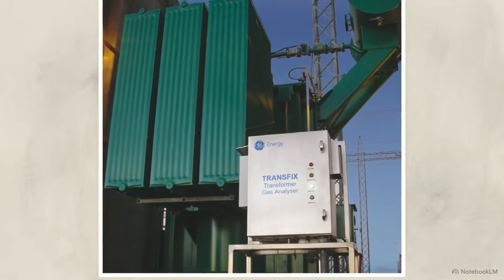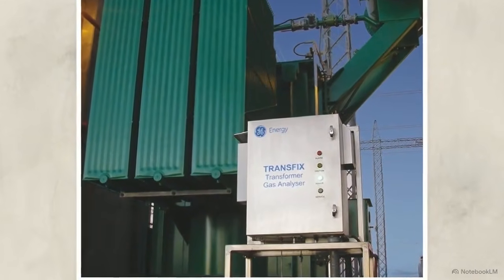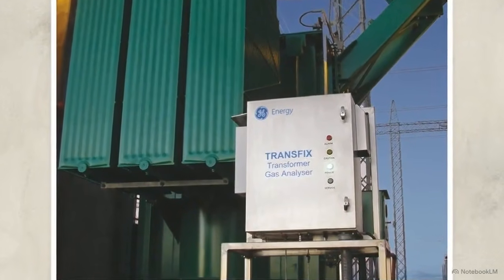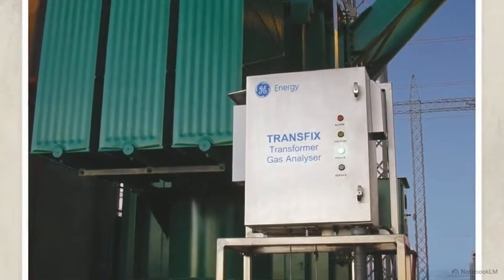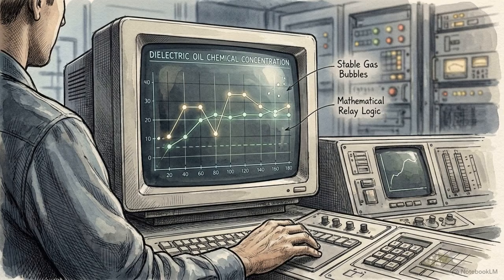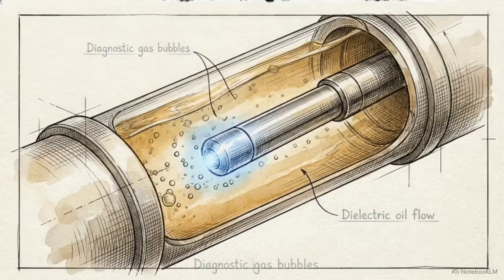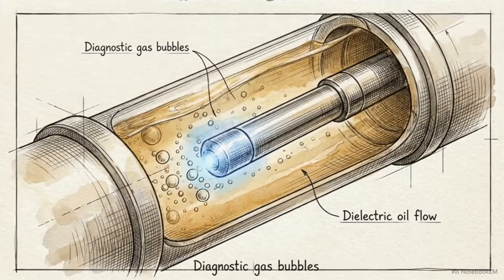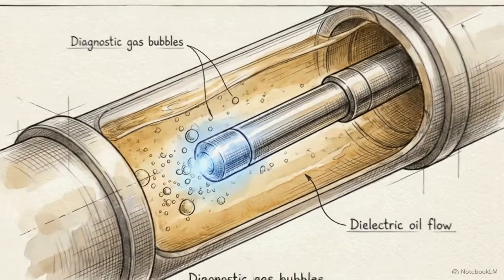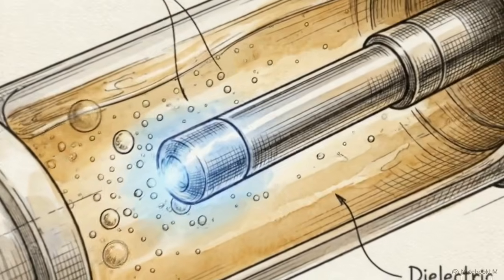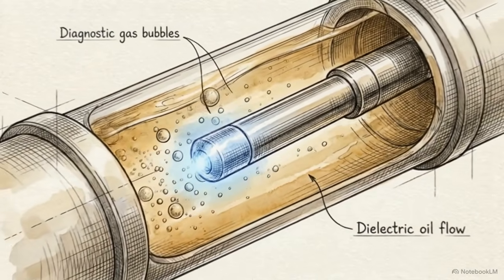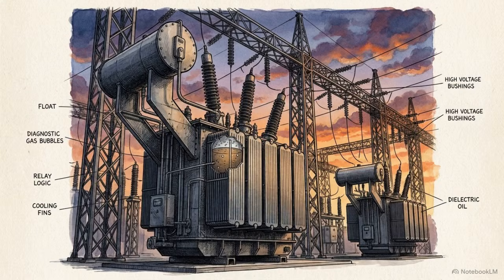Looking at this GE Transfix gas analyzer mounted on a modern unit, we can see the next evolution of this concept. Today's grid architecture supplements physical relays with continuous, online dissolved gas analysis. These advanced sensors continuously sample the oil, digitally tracking the exact same chemical signatures that the mechanical Buchholz trap catches manually. Securing the backbone of the power grid requires translating the invisible, microscopic chemistry of failure into these precise mechanical traps and mathematical defenses.